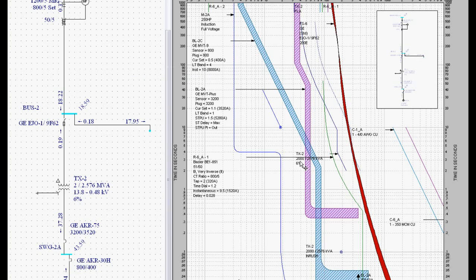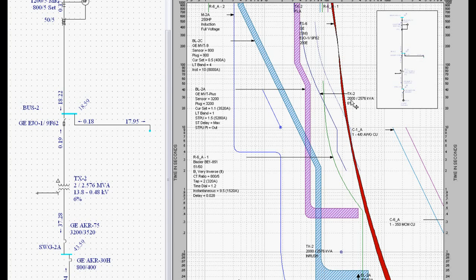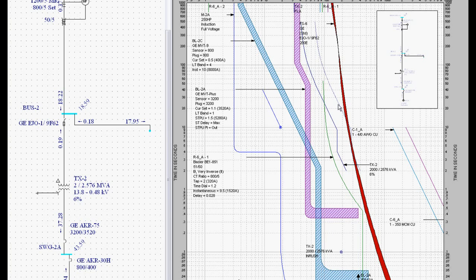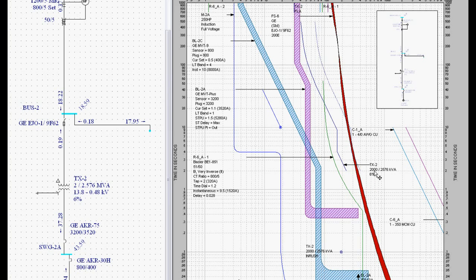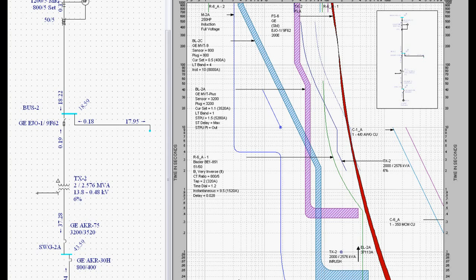Notice that here is this damage curve. That's what we were plotting. That's the 58% damage curve. Here's the 100% damage curve. So all that information is there. Here's the magnetizing inrush for this transformer. Here are the short circuit currents through each device.